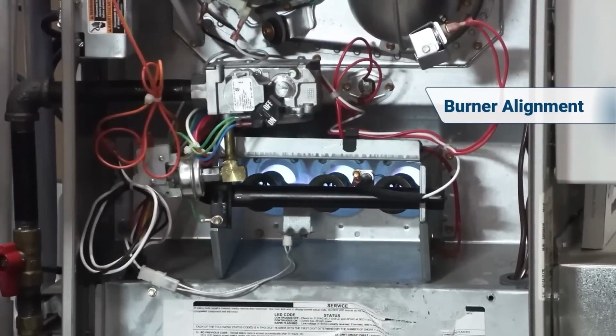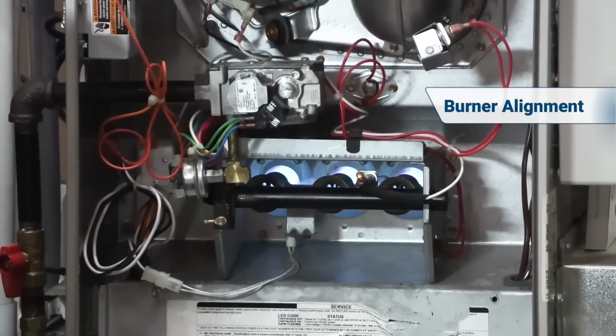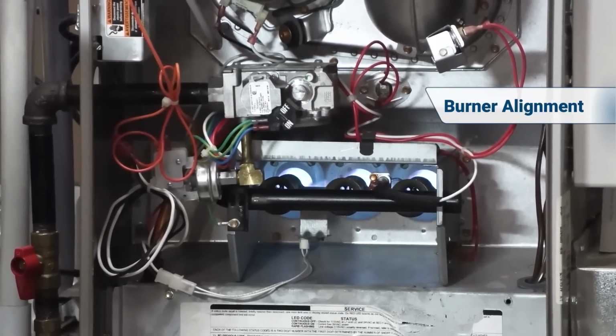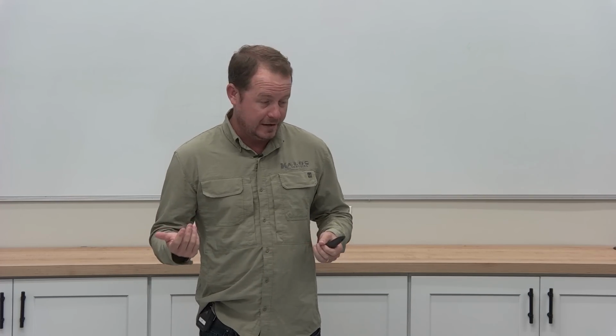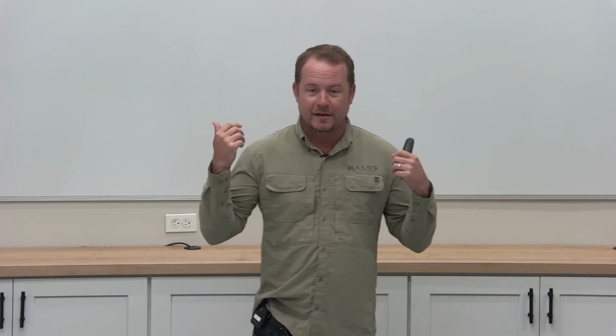I'll give you some more. So, alignment of the burners. In a lot of cases when you install a furnace, something gets a little tweaked sideways, and when you run that furnace, which by the way, we need to do every time we do maintenance on a gas appliance, every time we install a gas appliance. I know it sounds obvious, and people in other markets are going to laugh, like, why on earth would you do it? But we just don't think about heat a lot. We just don't have it in our head.